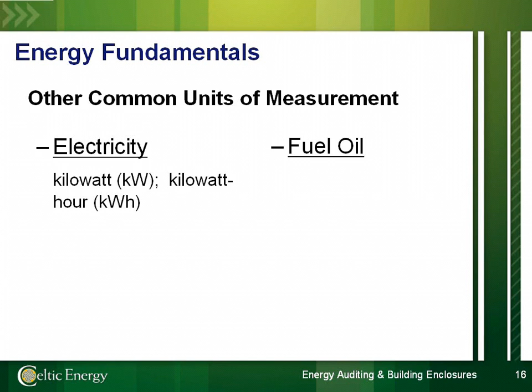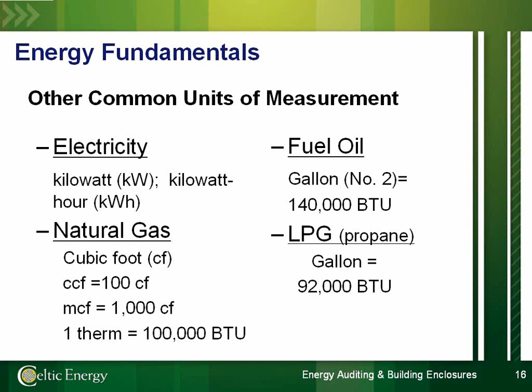There's fuel oil, which virtually everyone is familiar with. This is measured in gallons, at about 140,000 BTUs per gallon. Natural gas is measured in cubic feet, with about 100,000 BTUs per therm. Liquid propane isn't used as often, but that's about 92,000 BTUs per gallon.